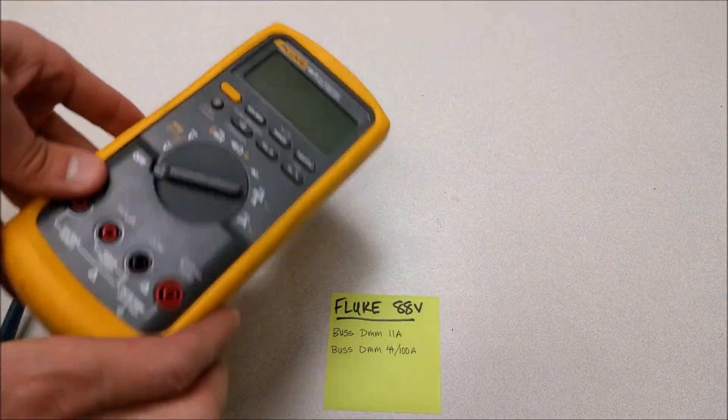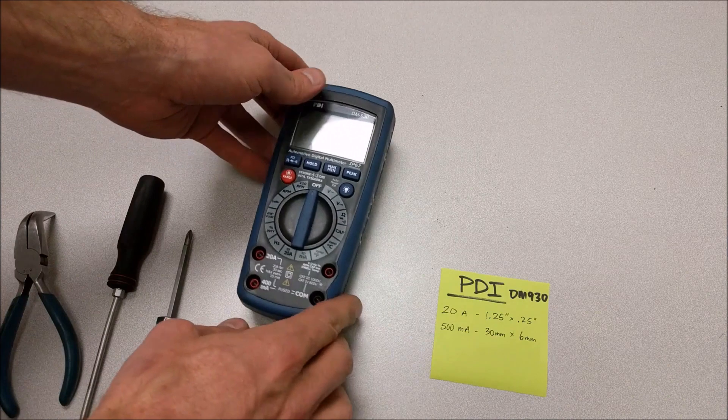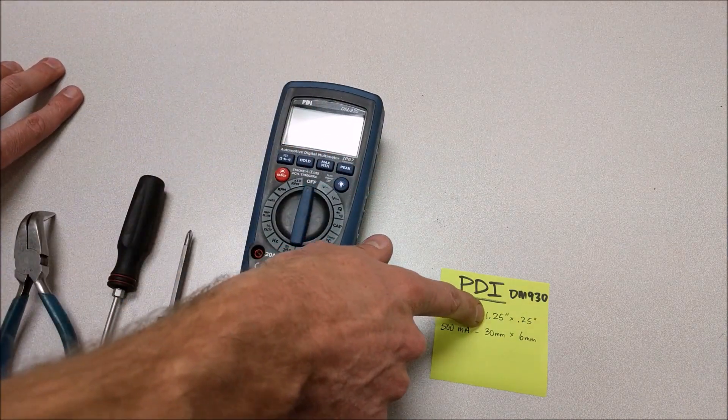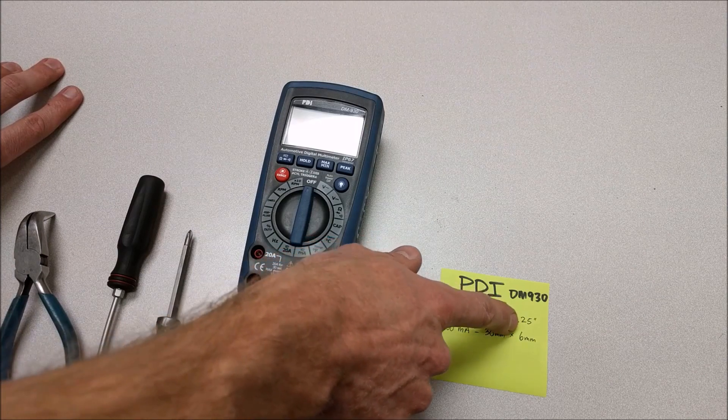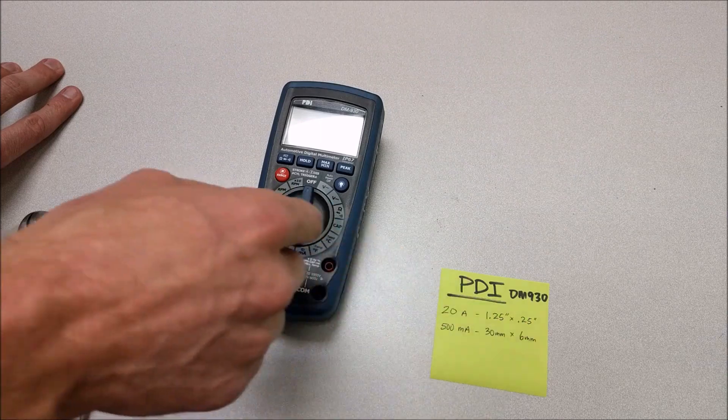Next, we'll do the PDI multimeter. These are the fuses we'll need for the PDI meter. We have a 20 amp fuse and a 500 milliamp fuse in this meter. One is a 1.25 by 0.25 inch fuse, and the other is a 30 millimeter by 6 millimeter fuse.